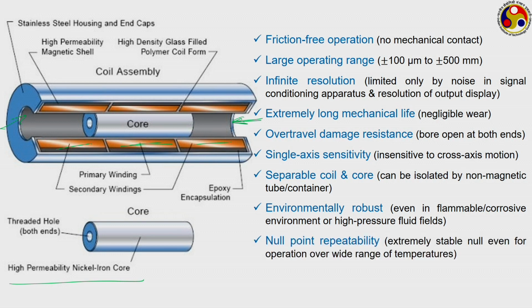Null point repeatability. The null position is very important, because when the core is not subject to any displacement, we should get a zero voltage, which we refer to as the null point or null position. The null position is highly repeatable even after several fluctuations. Even when the instrument is repeatedly changing position and then going back to null, it is able to reproduce the null quite regularly with high accuracy. It also doesn't suffer much from changing operating temperatures. The null position is generally retained even at very high temperatures.